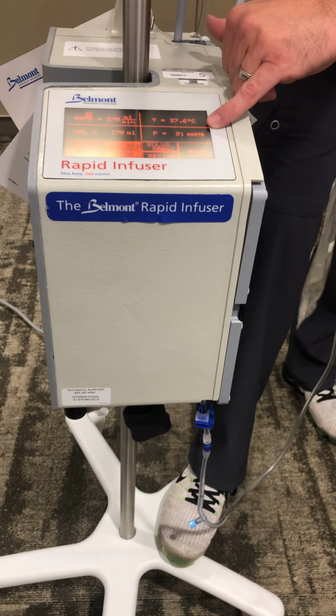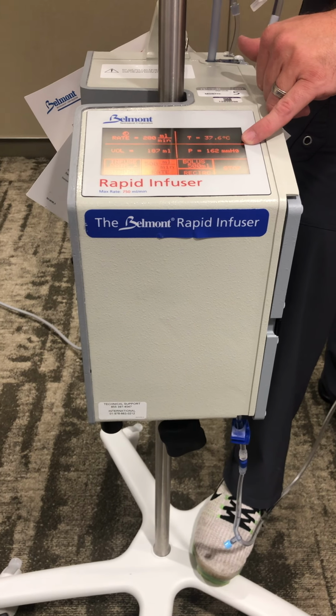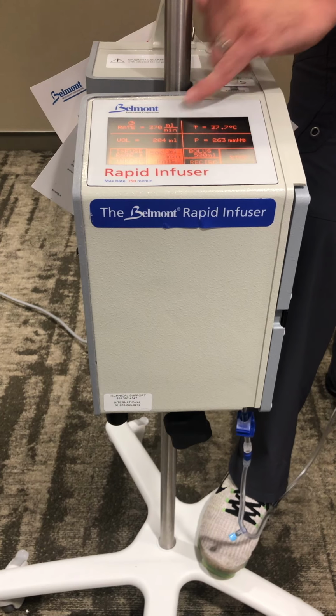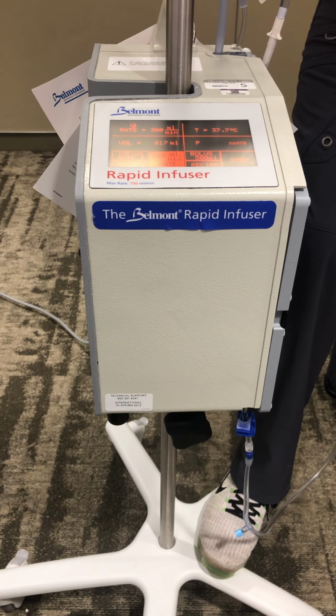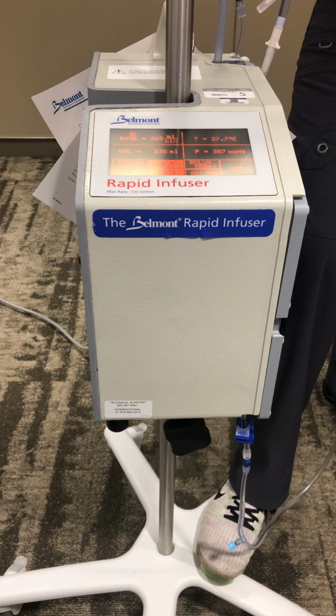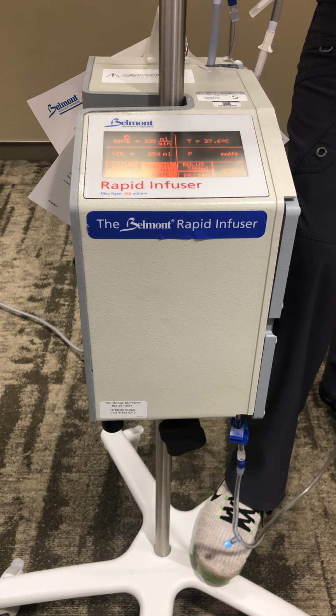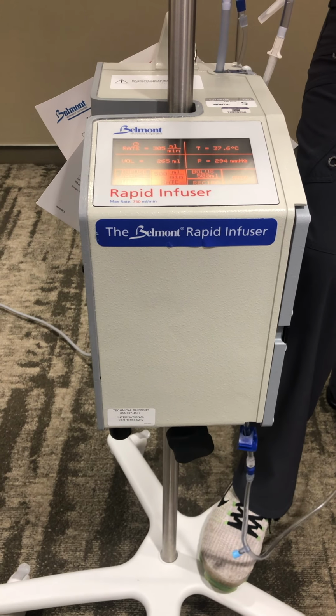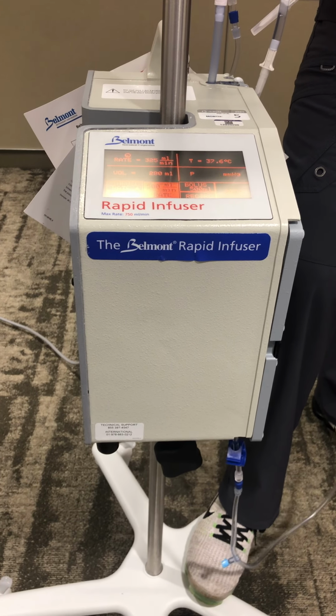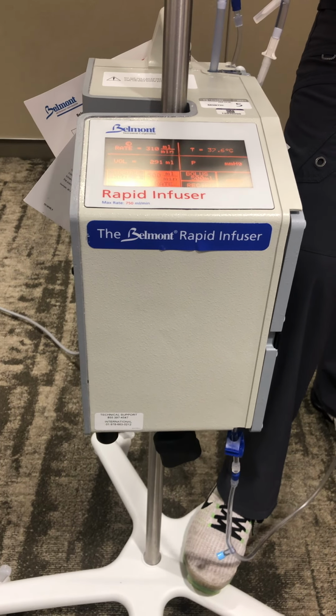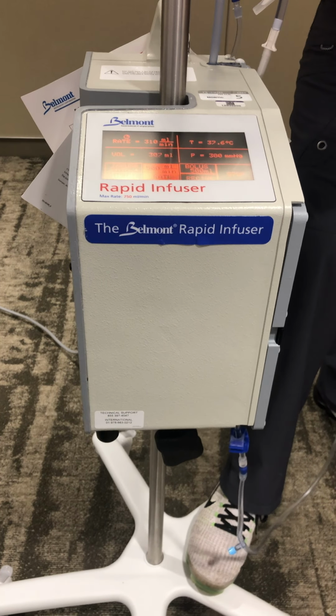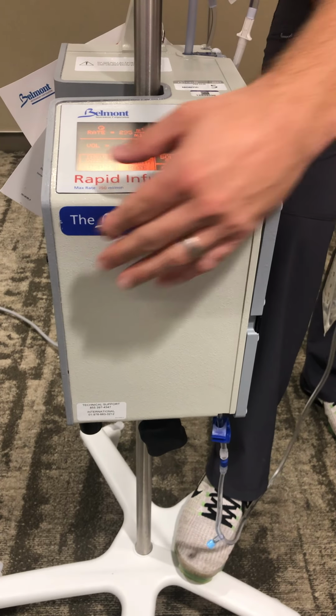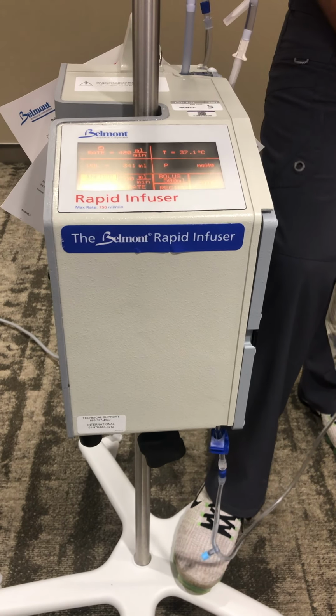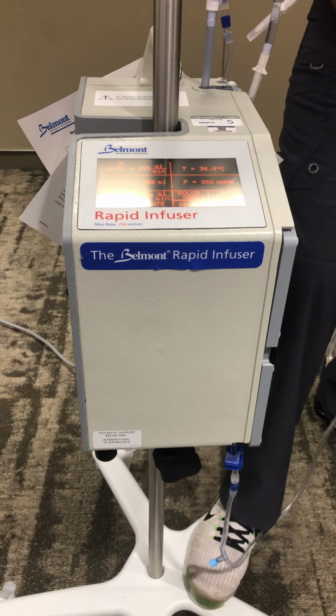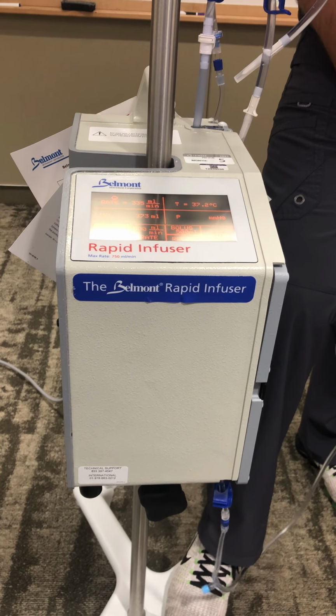Watch as this pressure grows and reaches 300, and see what it does to the 500 I've told it to do. See how it starts beeping and flashing? That's the pressure control regulating itself. Whenever the pressure gets too high, it drops the rate back down to release pressure, then rate, then pressure again. To silence that alarm, you'd have to manually scroll down to whatever number it was regulating itself to. Obviously it'd be more consistent with the catheter in there than me pinching it, but I think you get the point. It will keep beeping at you.